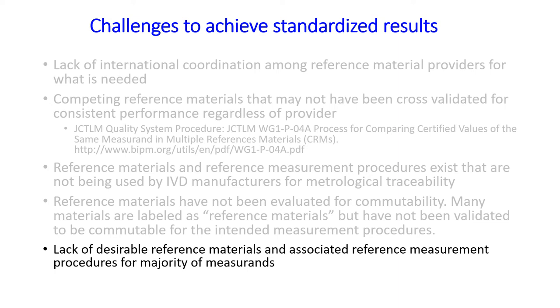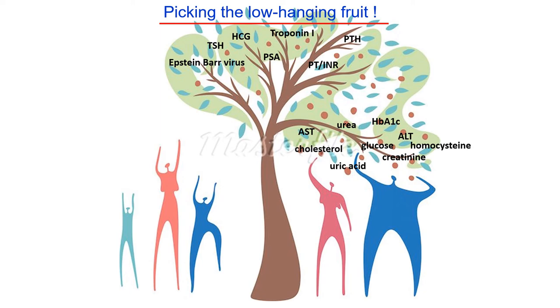Unfortunately, the number of measurands that can be standardized is fairly limited in relation to the thousands of different measurand tests performed in laboratory medicine. The reasons for this are the lack of clearly defined measurands, reference methods, and/or reference materials. Only 180 measurands have at least one reference material listed in the JCTLM database, and only 160 measurands have at least one reference measurement procedure listed. For measurand standardization projects, we have been picking the low-hanging fruit — the relatively easy measurands to work on. Standardization of measurands located higher on the measurand complexity tree, such as PSA, PTH, or PT/INR, along with hundreds of others, are technically more difficult and costly to achieve.